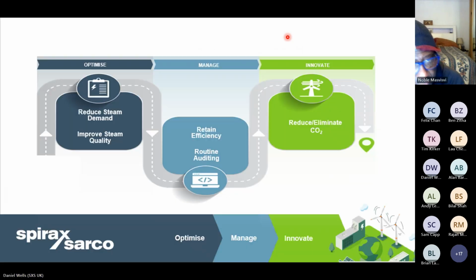But if we're transitioning from a steam system to a water-based system, all of those issues need to be taken into consideration. Okay, so when we're talking about a traditional steam system, I introduced the concept last week that that steam system could be 25, 30, 40 years old. So when that steam system was engineered, the cost of gas was cheap, the cost of water was cheap. No one had heard of carbon emissions. No one cared about carbon emissions or global warming. So the infrastructure was typically designed with a number of inefficiencies that we simply accepted back then. But today, the cost of gas and our environmental awareness means that we know where those inefficiencies are. So if we want to move towards a decarbonised steam system, we want to look at where those inefficiencies are and act on those inefficiencies first of all.